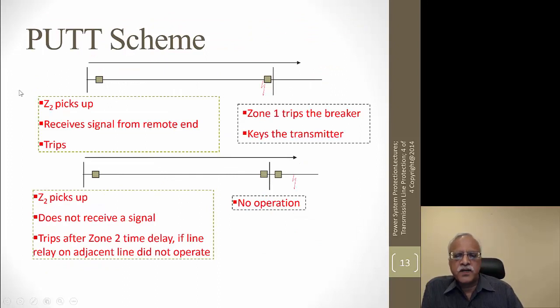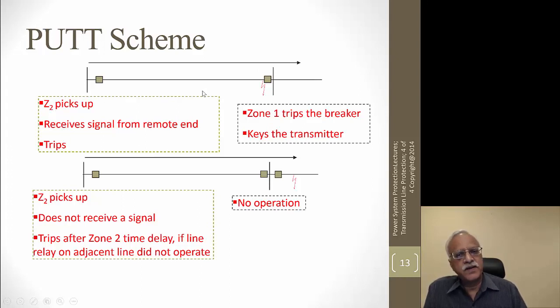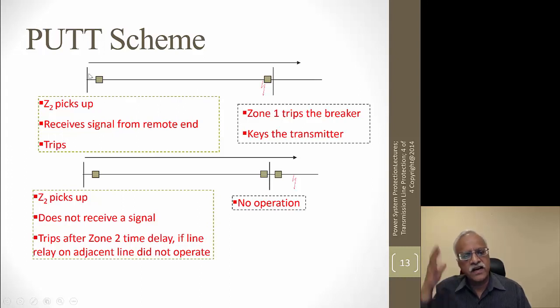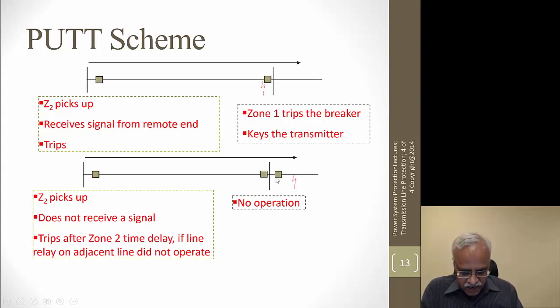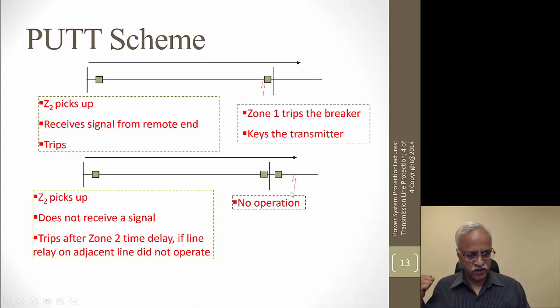In the permissive underreach scheme: if there is a fault on the line, zone 2 picks up. Zone 1 trips the breaker and keys the transmitter, sending a signal to the remote end. At the remote end, zone 2 has picked up but does not trip immediately due to its time delay. As soon as it receives the signal from the remote end, it trips. The delay in tripping is just the communication time from station B to station A. If there is a fault outside the line section, there is no relay operation at station B because the fault is behind — there is no reverse-looking relay.